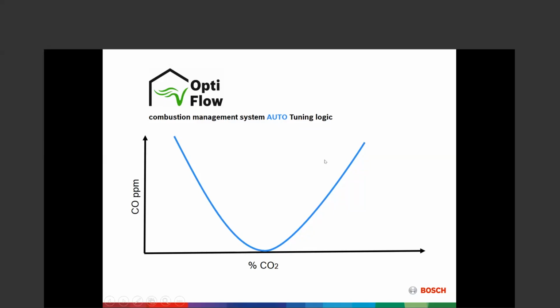You can see that the CO can be high, whether we're over here at low CO2 or over here at high CO2. So how does this unit do this without a combustion analyzer? Interestingly, the ionization current, so that's the current that we see through the flame sensor, the rectification current through the flame sensor, also moves in the same fashion as the percent CO2.